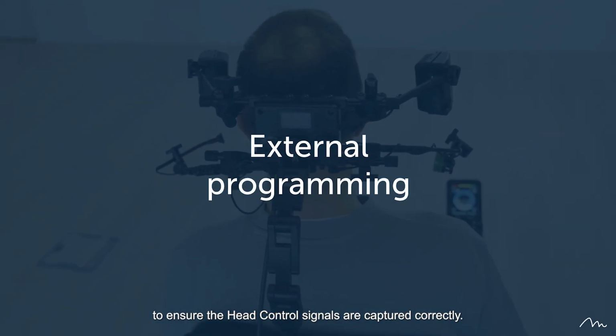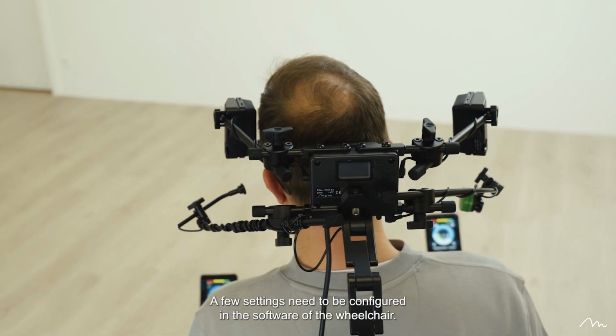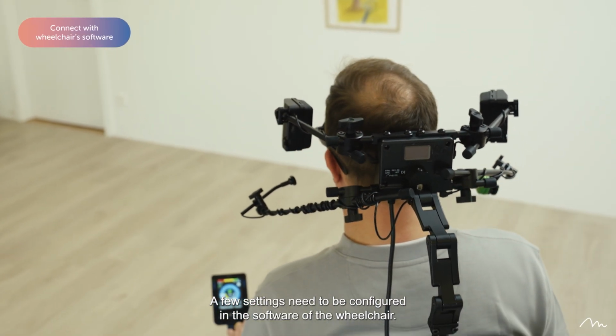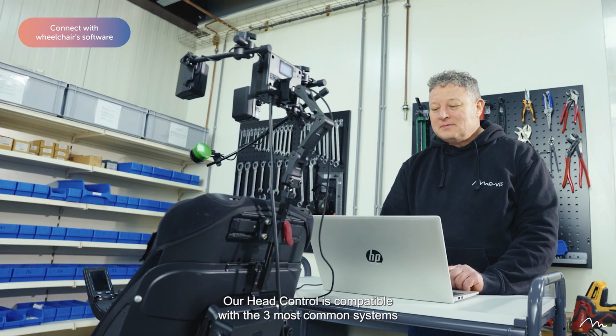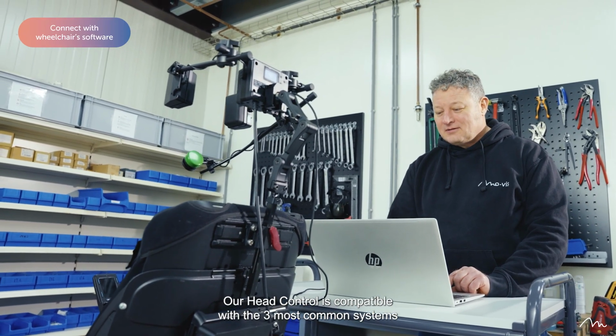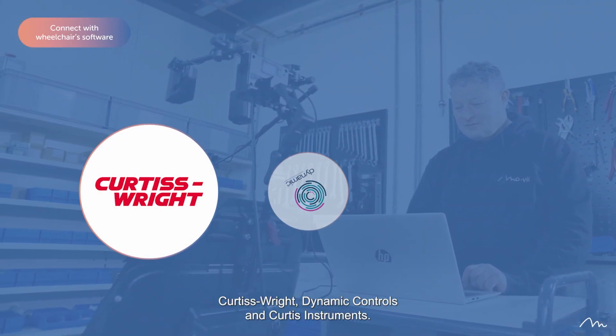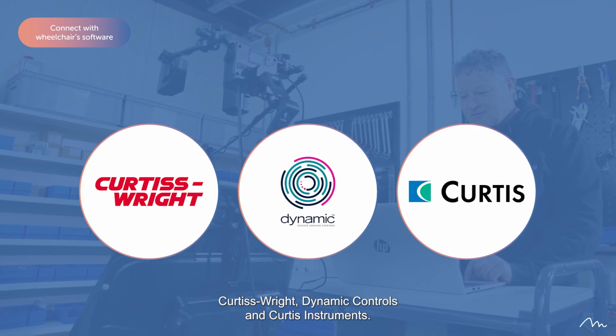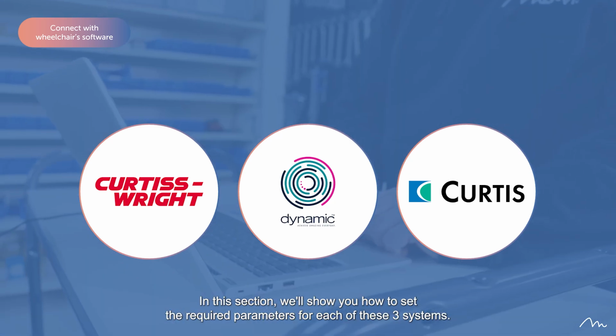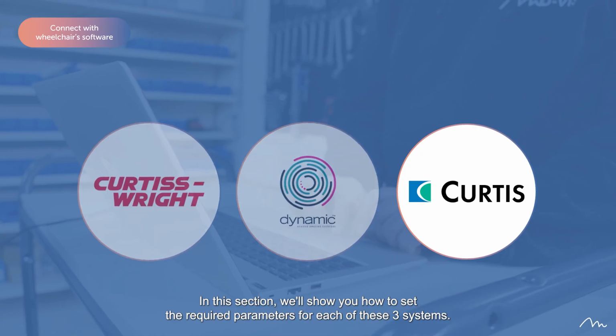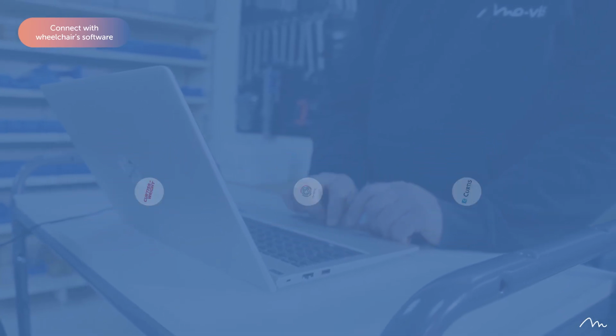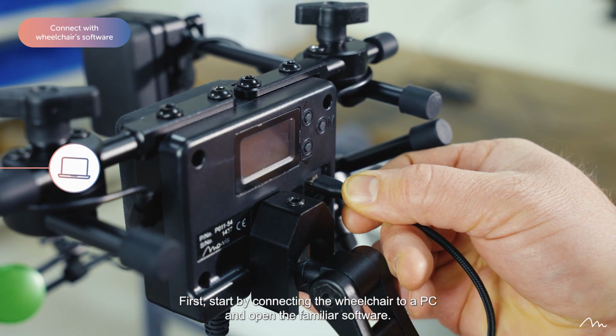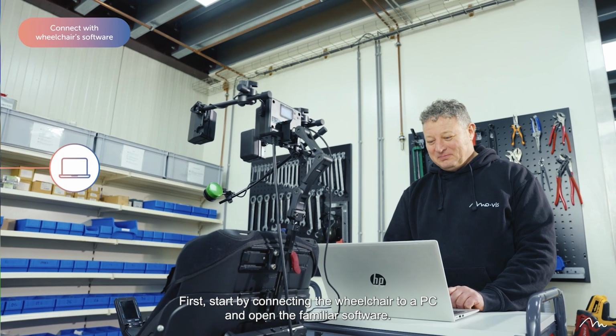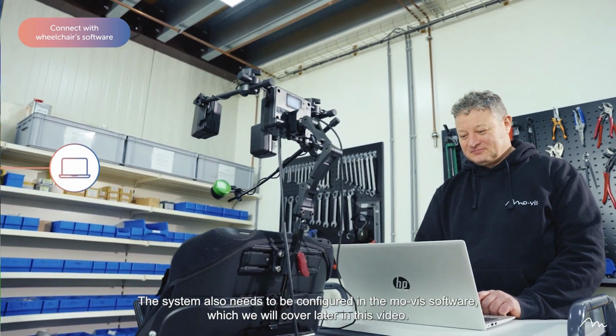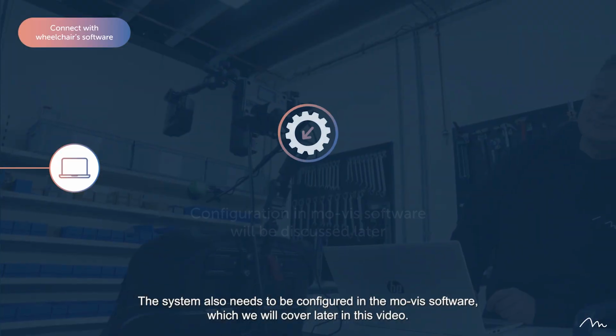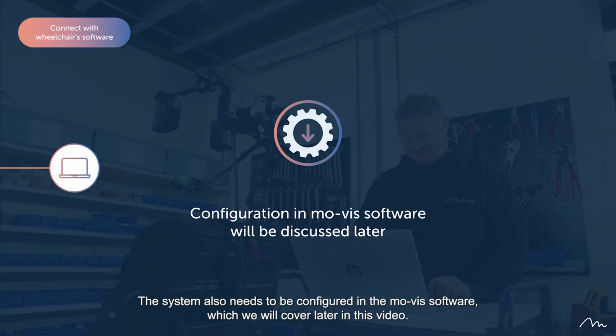To ensure the head control signals are captured correctly, a few settings need to be configured in the software of the wheelchair. Our head control is compatible with the 3 most common systems: Curtiss-Wright, Dynamic Controls, and Curtis Instruments. In this section, we'll show you how to set the required parameters for each of these 3 systems. First, start by connecting the wheelchair to a PC and open the familiar software. The system also needs to be configured in the mo-vis software, which we will cover later in this video.